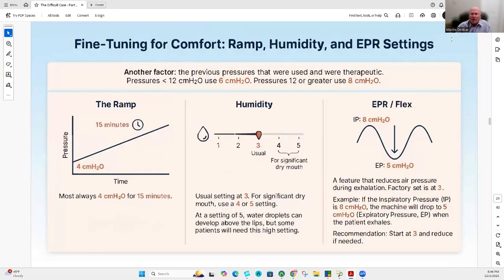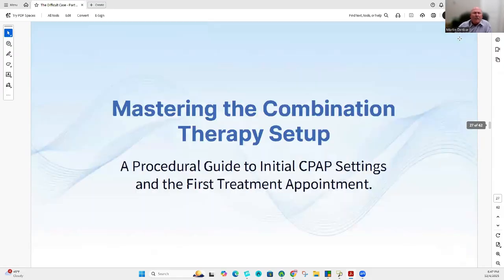Once in a blue moon, someone will say, that's uncomfortable. So I'll go, great, we drop it from 3 to 2. Then I give them a week or two, then I drop it to 1. And I'll do high resolution pulse oximetry just to check the oxygen as I'm going down with the EPR. But most patients, when you have it set at 0, don't really complain, but occasionally they do. So be ready to adjust that as needed. Next.